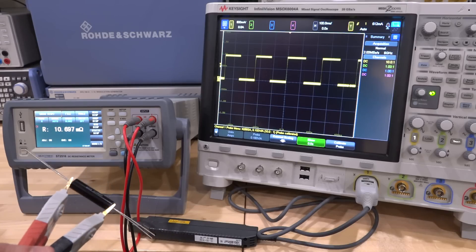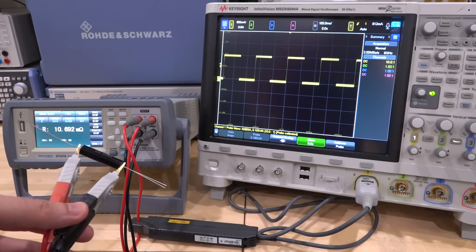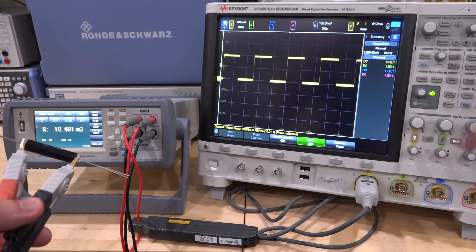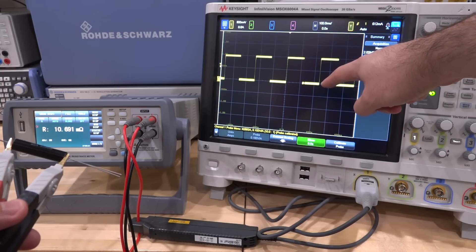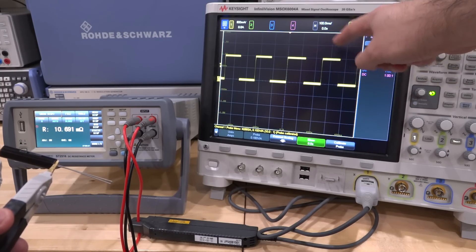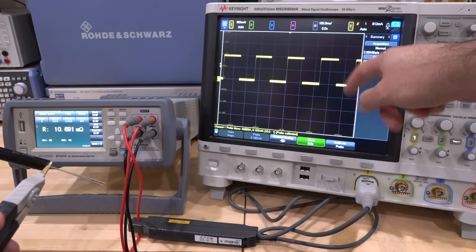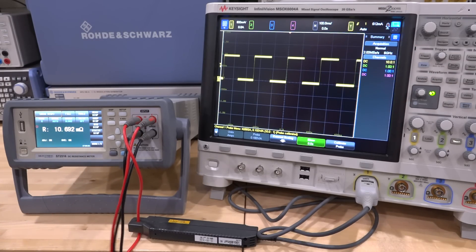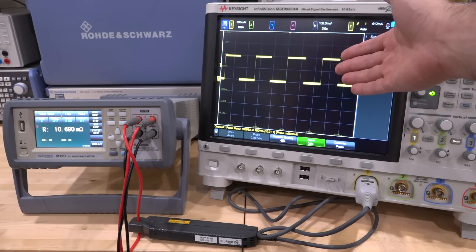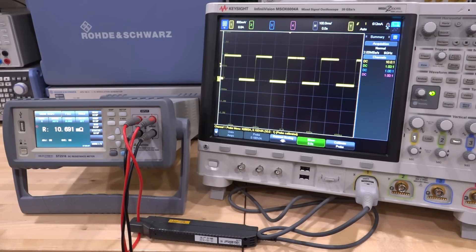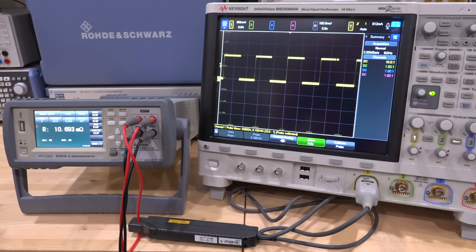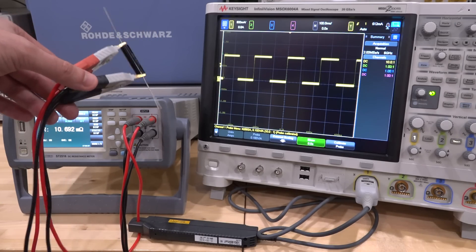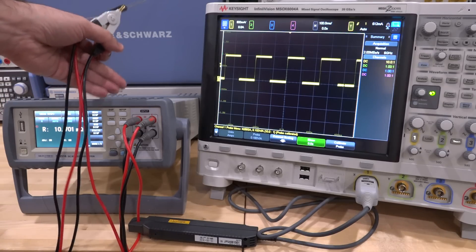Well that's because the force terminals and the sense terminals of this instrument for measuring resistance are separate and that's a big advantage because if you turn off the current and only use the sense port you actually can measure the voltage developed here and that voltage is going to be developed because of the bimetal interface, the thermoelectric effect. So basically what it does is that it constantly corrects for that. It does an open circuit measurement, measures the thermoelectric, then it pushes the current, measures it again, subtracts those values and then it calculates from Ohm's law what the resistance is. It's a very simple method to do this.